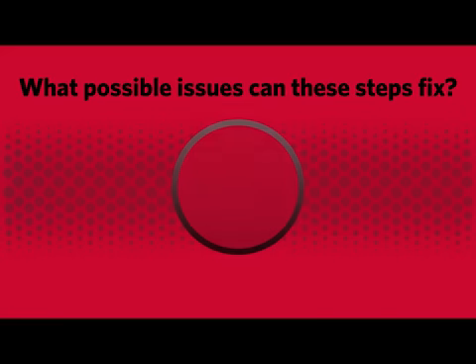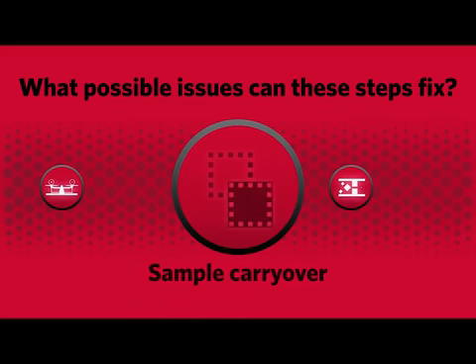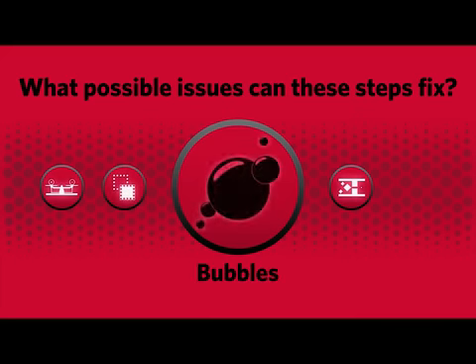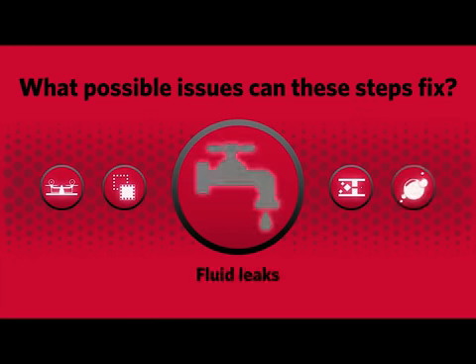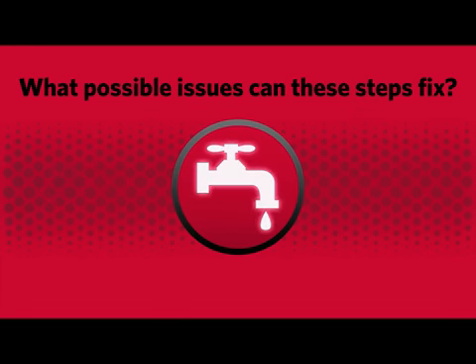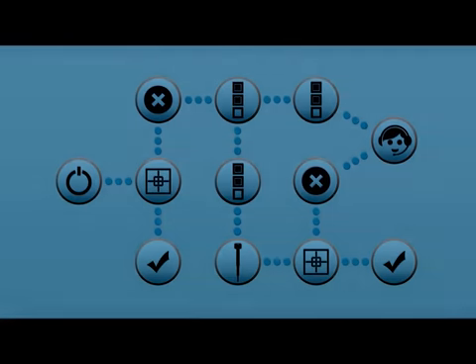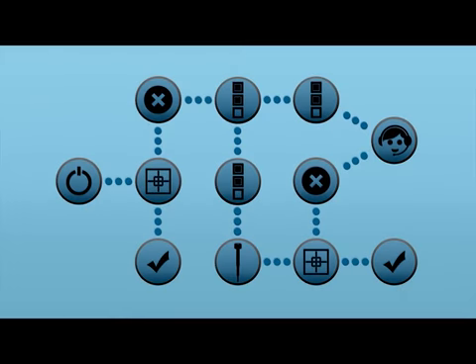These steps will only take a few minutes and can solve issues such as low or no microsphere count, clogs, sample carryover, bubbles in the line, certain fluid leaks, and many other issues you might experience while using the MagPix instrument. We will use this flowchart to guide our troubleshooting.